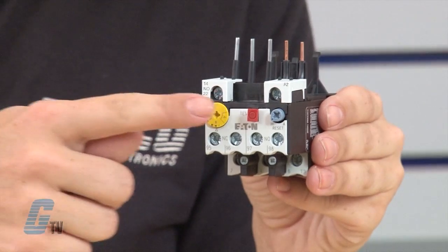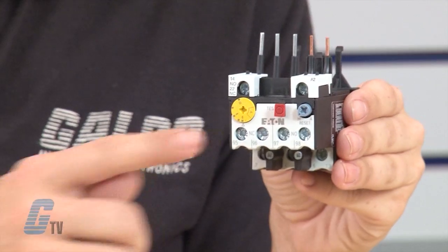The XTOB models are available in either contactor mounted or separately mounted versions. XT Series Thermal Overload Relays include a test button for simulating an overcurrent situation, normally open and normally closed auxiliary contacts, and a selectable manual or automatic reset.